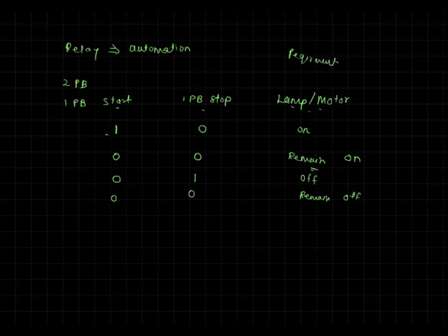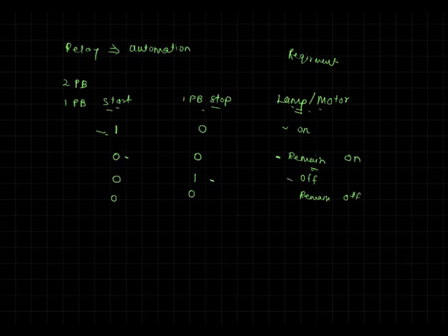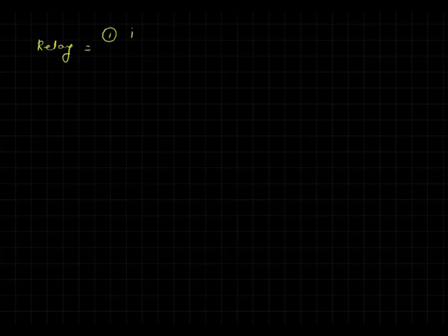This is my requirement: two buttons — start and stop — and one lamp. Now how can we use relays to perform this operation? A relay provides two key advantages: first, it provides electrical isolation — no direct contact between input and output. Second, it offers two contacts: one NO (normally open) contact and one NC (normally closed) contact, which can be used for interlocking.